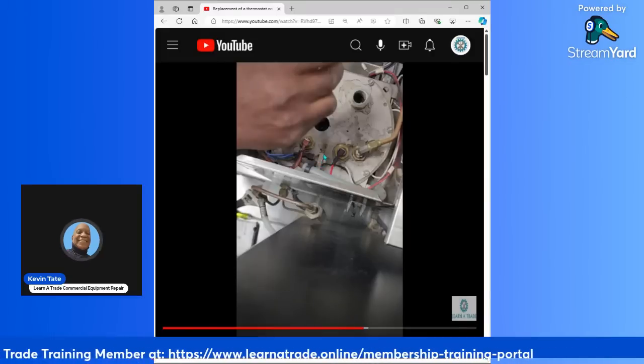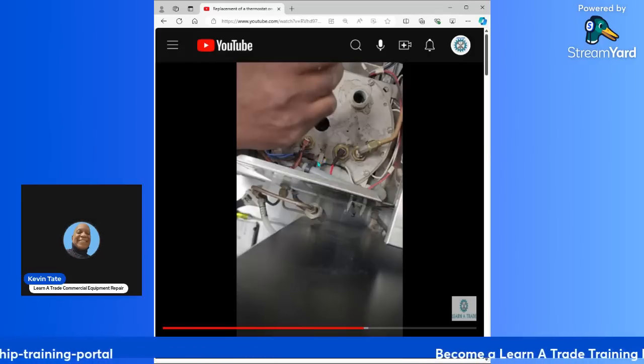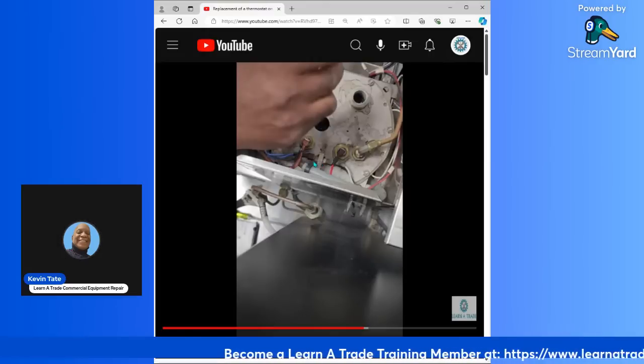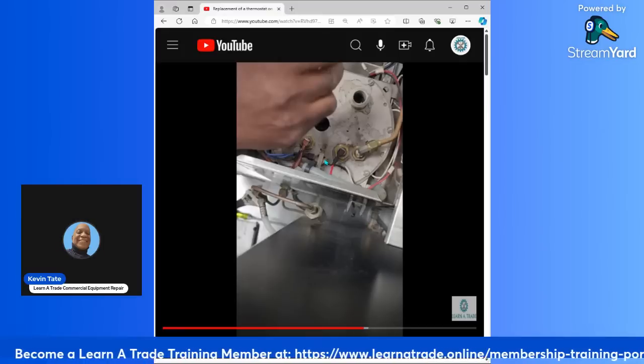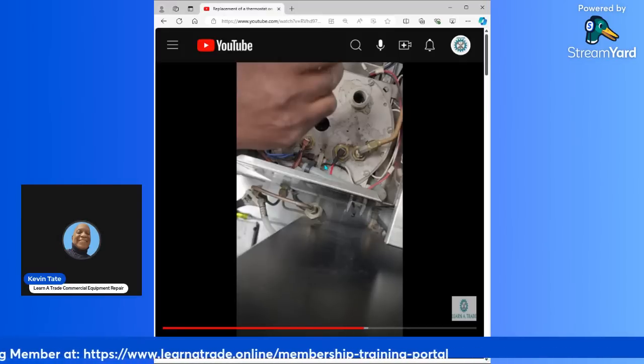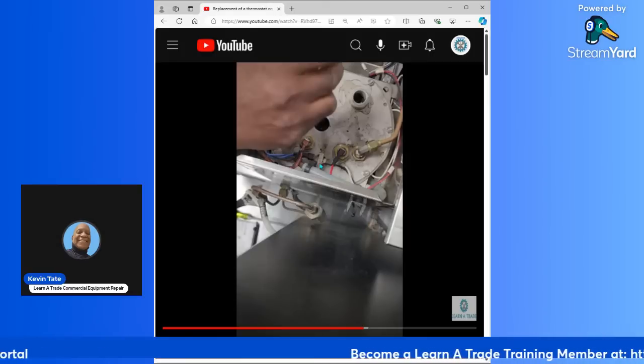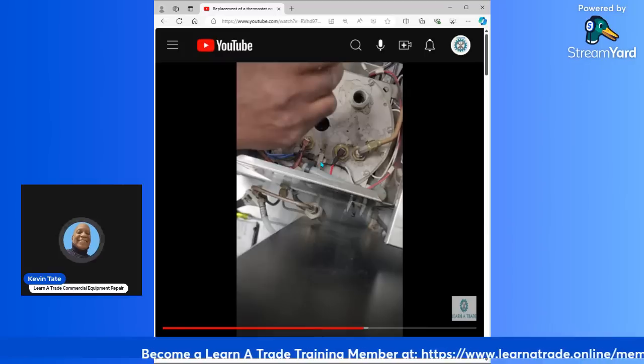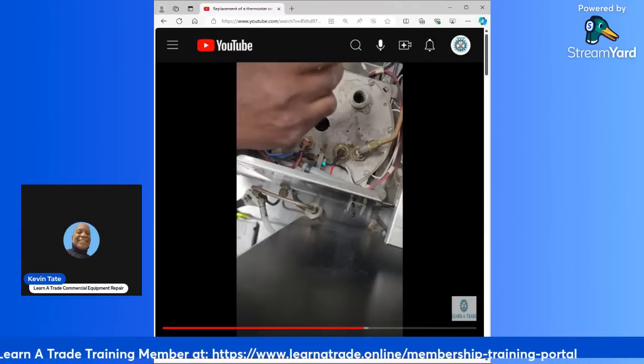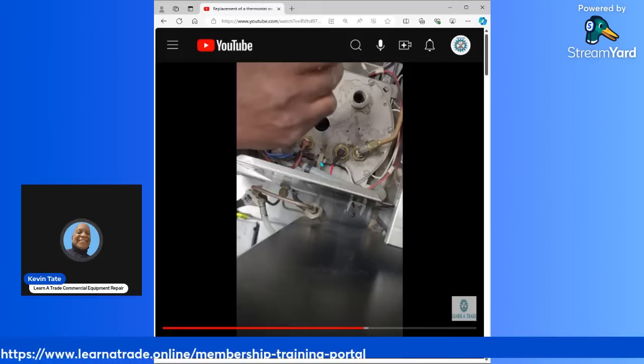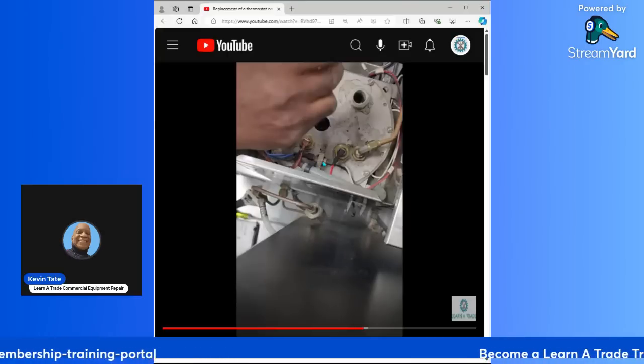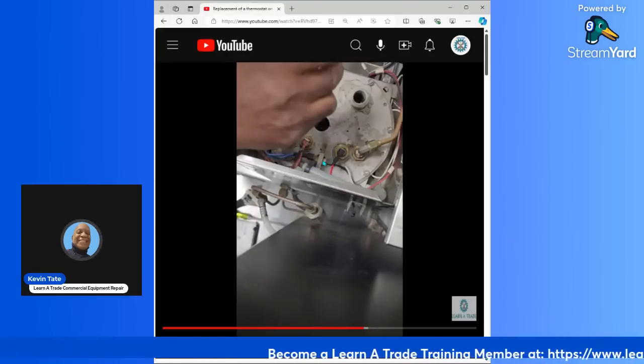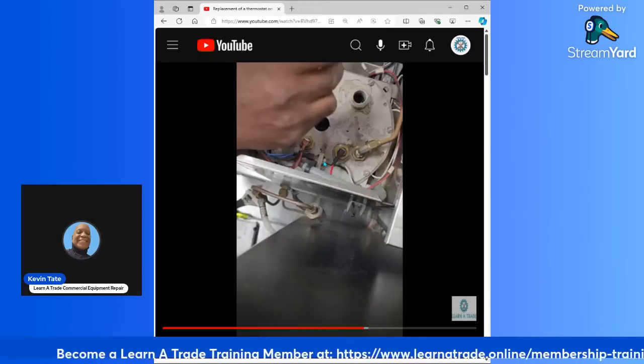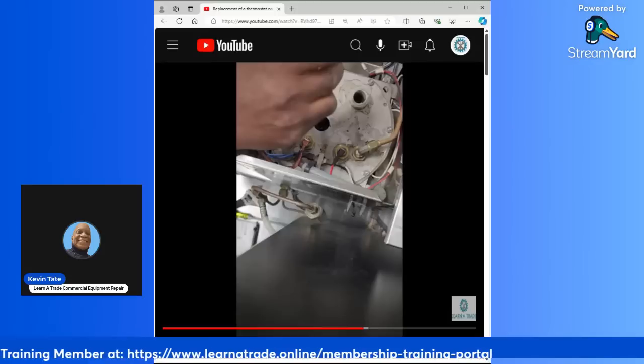And then right down here, this stainless steel clip is holding in my high limit probe, my high limit sensor. If it gets too hot, this high limit will cut in to turn off the heaters. Okay, if the thermostat's not working, this high limit will shut it off. Once it gets past boiling point, it'll shut off the heaters. What was happening was, I believe I changed this already. There was an old high limit on there, and the high limit was not good. So it was actually allowing the machine to boil over, and that's why they had constant leaks and steam.